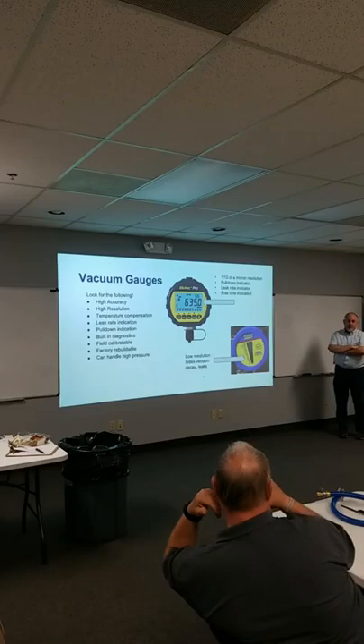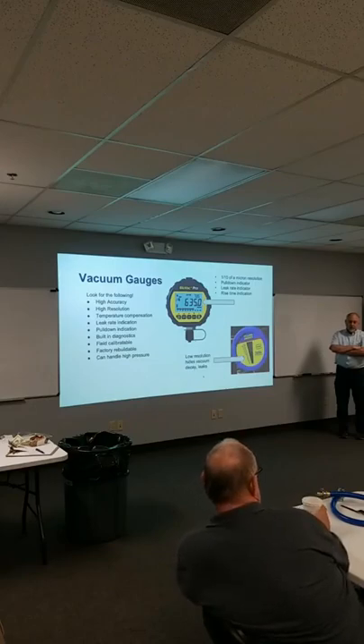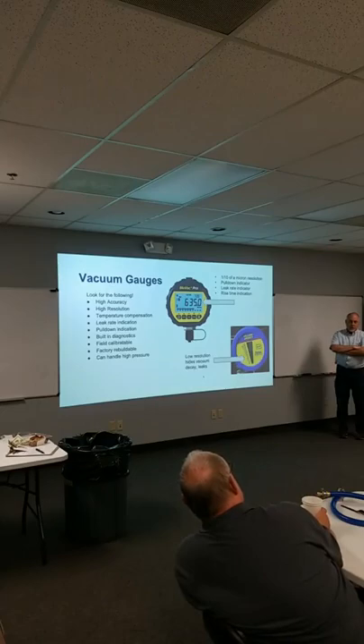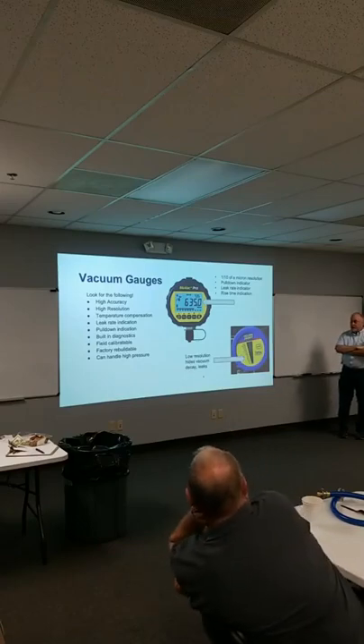You can't discount that. I mean, that's back at points in our industry, like if you look at the old vacuum gauges for doing chillers, they used to have almost like a refrigerant, it would change the temperature of the gauge as you were pulling the vacuum. Can't remember what it's called, the void gauge, or what the name of the gauge is. There's a lot of different ways of testing for vacuum. The challenge is all the gauges were inaccurate, you know, there's a lot of challenges with measuring deep vacuum. This is about the best way to go today, is a digital vacuum gauge.